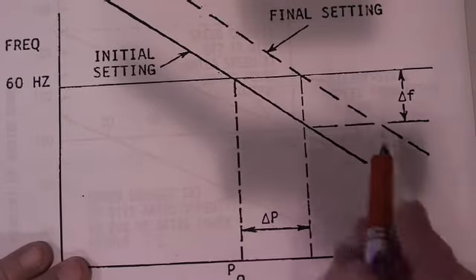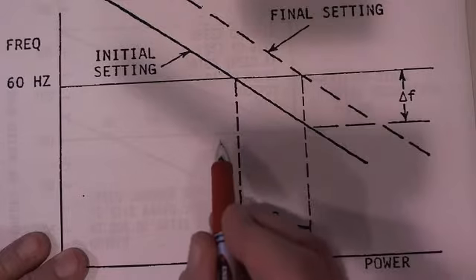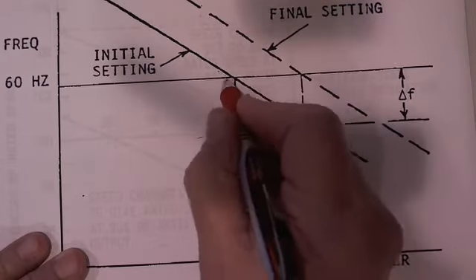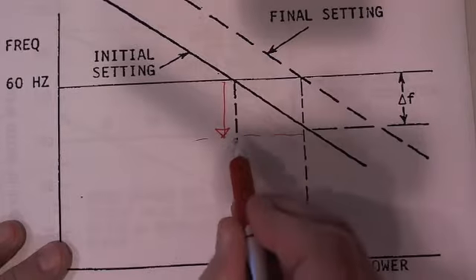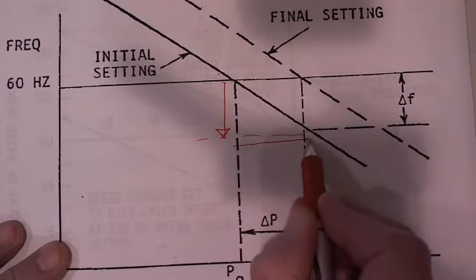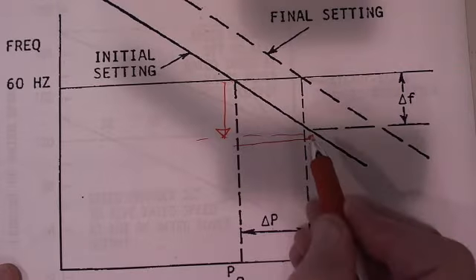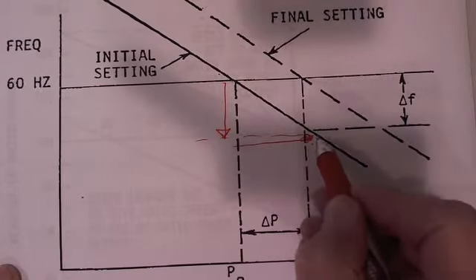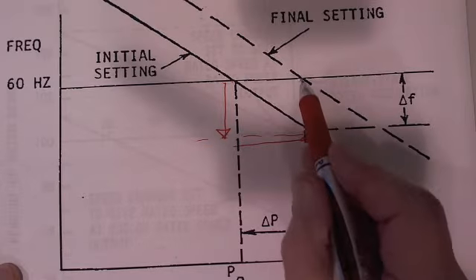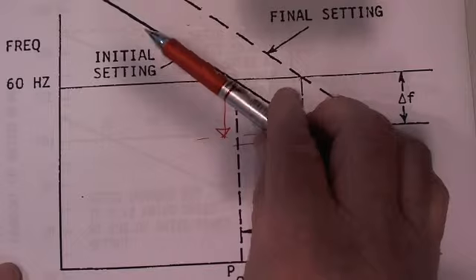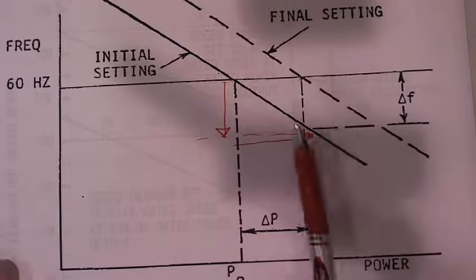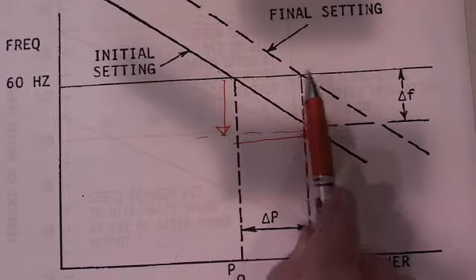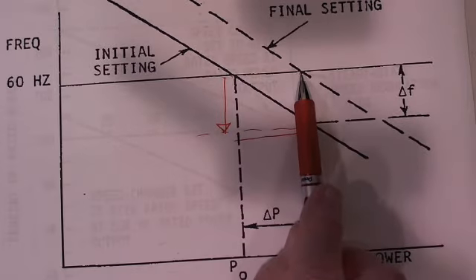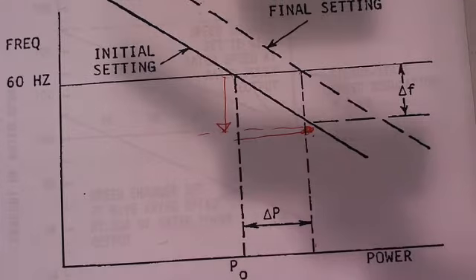So what I want to do now is say, okay, look, I got a frequency drop. So the frequency dropped to here, and the generation went over here. Now what I'd like is that much generation on this line, but I'd like to get the frequency back to 60. So I move this characteristic over, and now I'm getting the correct generation. I got more load, but I've raised the frequency back to 60 hertz. And that requires some sort of central device.